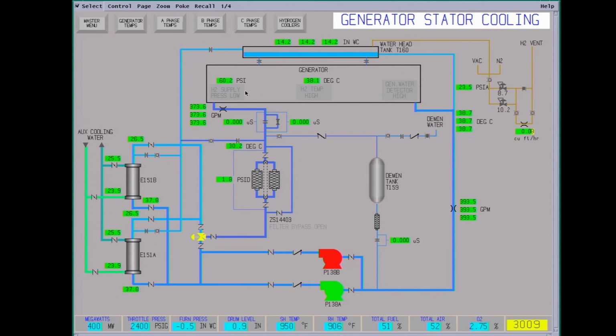This unit also has hydrogen on the shell side of it. Right now running 60 psi hydrogen pressure inside the generator. It's 38 degrees Celsius. There's water detectors on the bottom of the generator shell looking for any leaks in the hydrogen coolers. So this water here goes up to the generator.